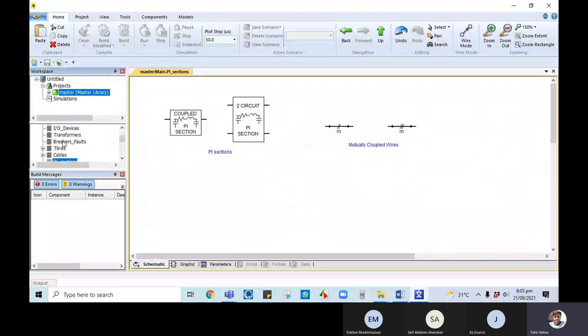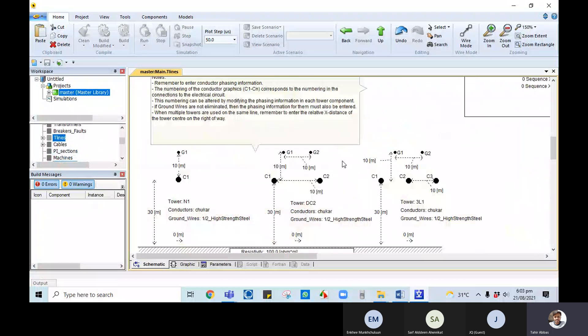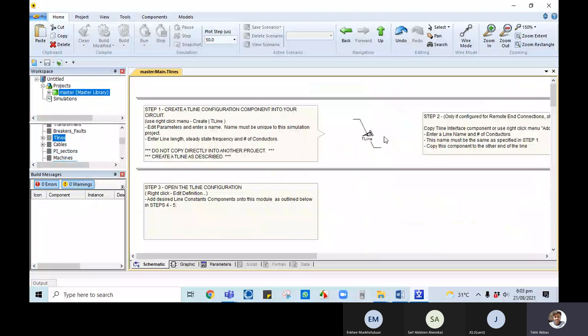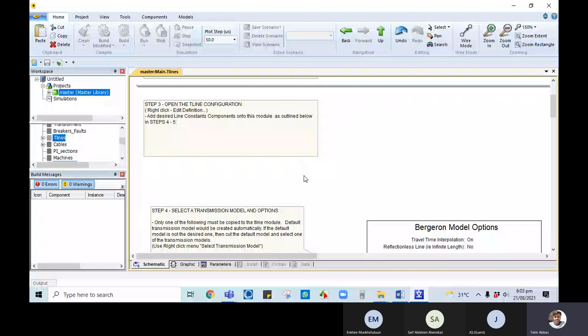In the transmission line master library under T-line, based on conductor information and different models — frequency dependent or others — and based on the tower data, such as tower type and clearance between conductors, we can make use of these models to get parameters. Most importantly, if we are performing load flow analysis or modeling a line for a steady-state problem, it is fine to just use the pi section from the master library.